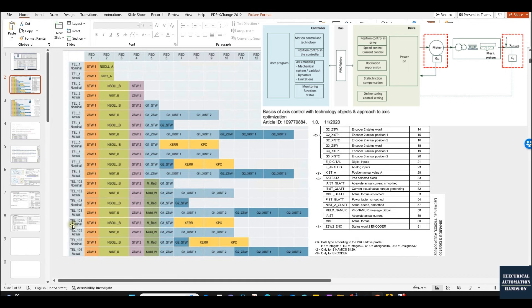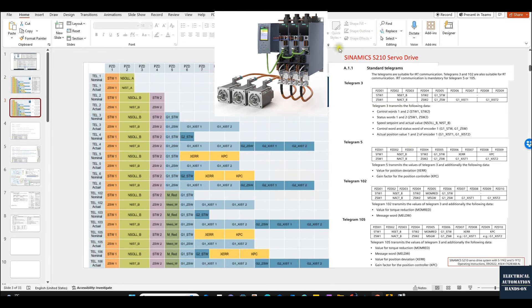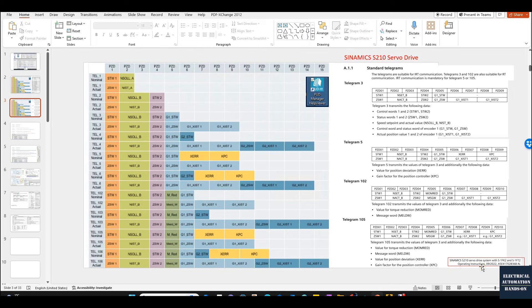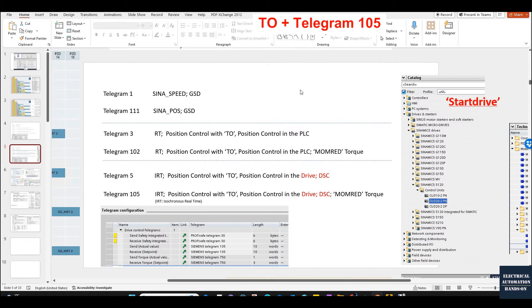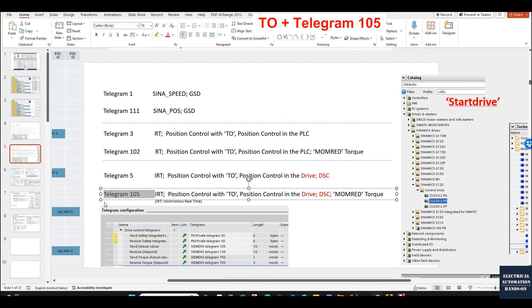If you are using the SINAMICS S210 servo drive — the middle-end servo drive system — this page comes from the S210 operating instruction manual. When you look at this you may also feel confused about the differences. I would say when using Siemens motion control VFDs or servo drives, 90% of the time you will select the telegram from this page. As I introduced, most cases use telegram 105 — the very standard Siemens servo drive positioning control telegram. It is based on IRT communication: isochronous real-time. While using telegram 105 we can use the technology object (TO) to configure the drive.